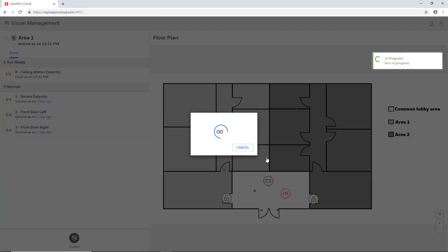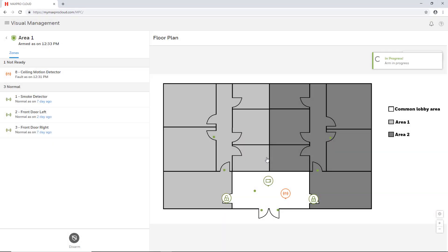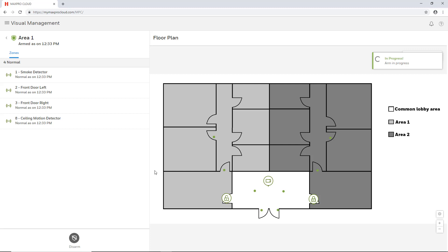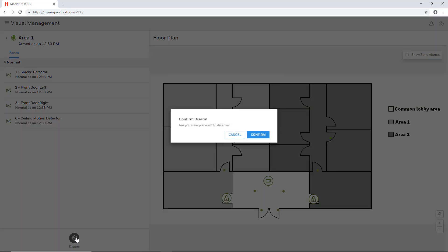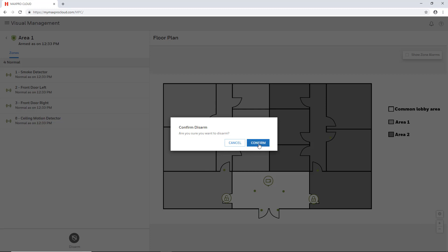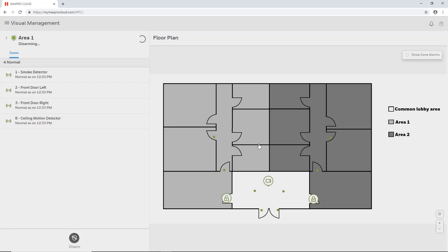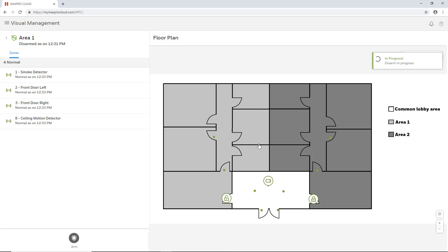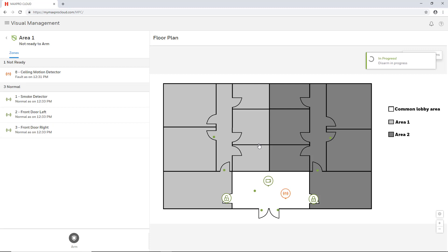Disarming is done in the same manner, but uses the disarm button instead and will show if the area is armed. If an alarm has occurred, two disarms must be performed to acknowledge and clear the alarm. After the first disarm is complete, the button will change to a reset button, which will allow the second disarm.